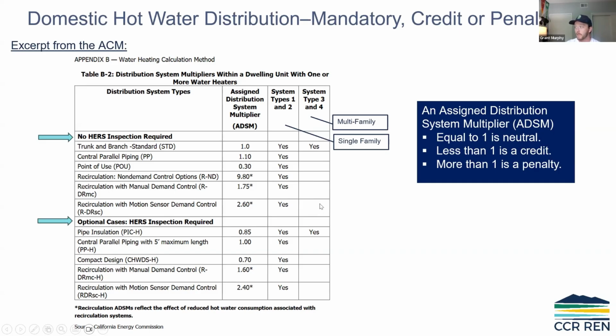So for a lot of single family residences, it makes it really hard to comply when you have recirc non-controlled. And the code, what it's doing - if you can see by these values, they applied all these distributions - one would just be code, so anything less than one you're getting credit, anything over is a penalty. They want us to do a manual push-button demand control at every fixture, or a motion sensor - I don't recommend those - but you can see there's still a penalty, just not as bad as an uncontrolled one.